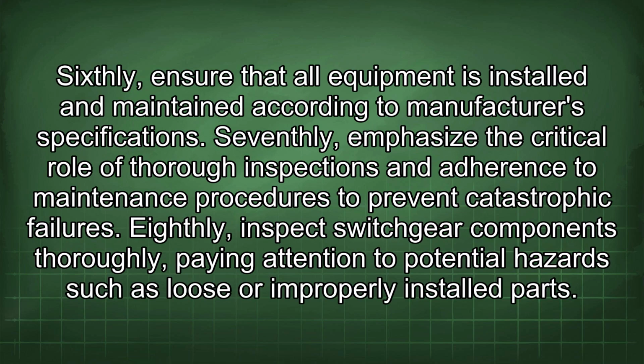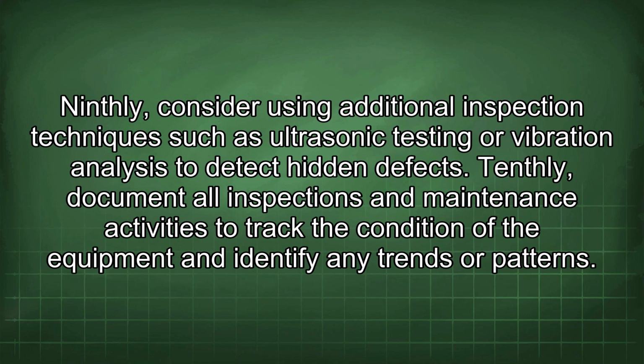Sixthly, ensure that all equipment is installed and maintained according to manufacturer specifications. Seventhly, emphasize the critical role of thorough inspections and adherence to maintenance procedures to prevent catastrophic failures. Eighthly, inspect switchgear components thoroughly, paying attention to potential hazards such as loose or improperly installed parts. Ninthly, consider using additional inspection techniques such as ultrasonic testing or vibration analysis to detect hidden defects. Tenthly, document all inspections and maintenance activities to track the condition of the equipment and identify any trends or patterns.